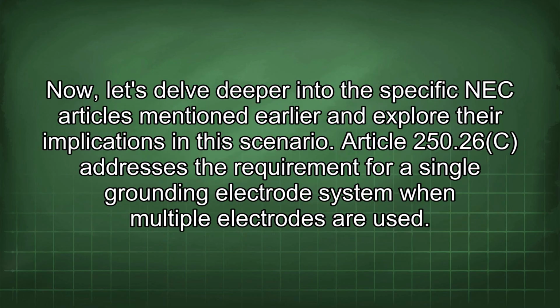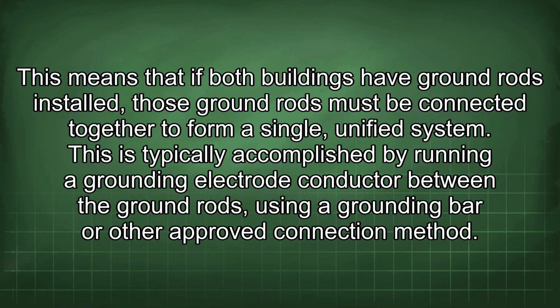Now let's delve deeper into the specific NEC articles mentioned earlier and explore their implications in this scenario. Article 250.26(c) addresses the requirement for a single grounding electrode system when multiple electrodes are used. This means that if both buildings have ground rods installed, those ground rods must be connected together to form a single, unified system. This is typically accomplished by running a grounding electrode conductor between the ground rods, using a grounding bar or other approved connection method.